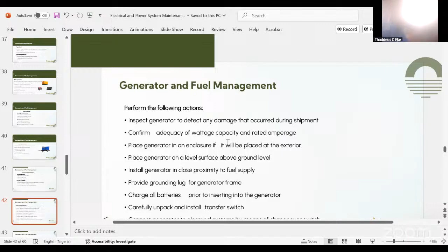You can see wattage here - check before you accept the generator, whether the power rating conforms to what you have determined and recommended. If it's short of that, you have the right to reject the generator until they supply the right capacity. Never compromise, because the seller just wants to sell. Once they sell, they will leave you to your problem, and you'll be the one running up and down. You cannot come back to your management and say the generator requested was not what was delivered, because you are in charge - you are the person that will receive and make sure installation is done how it's supposed to be done.